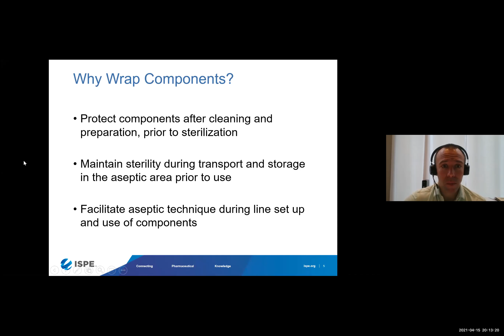In order to make this happen, we really need to have well-defined procedures. And of course, these procedures are supported by validation. In the last webinar, if you were able to join, we talked about the autoclave process validation itself, but really the focus of regulation has moved beyond the scope of just autoclave or sterilization validation. The scope has changed to include the parts preparation, so that's using the sterilization wrapping, all the way through the transport, storage, and unwrapping. So the procedures that we're writing up for sterilization wrapping or parts preparation need to be well defined and validated.